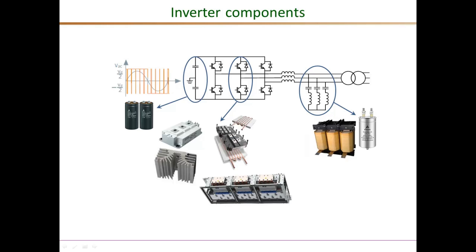Because of the high switching frequency, we need to filter the high-frequency components, and these are the LCL filters that remove those components. On the DC link, there is a bank of large electrolytic capacitors to keep the DC voltage smooth, and especially in single-phase applications, to support the 120 Hz power pulsations.